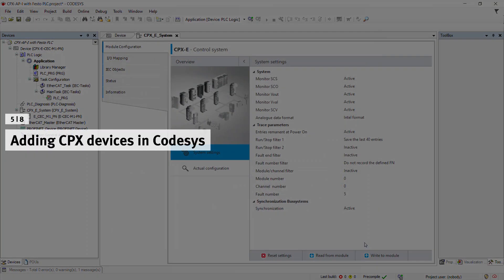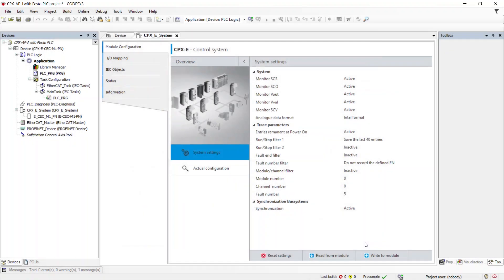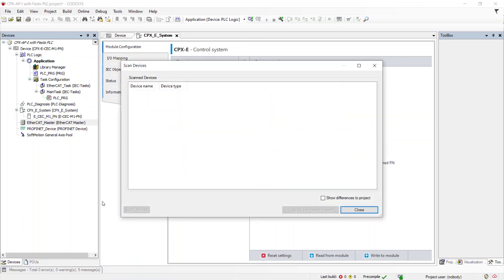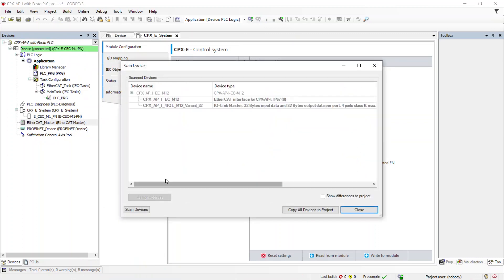Adding CPX devices in Codesys. Right-click on EtherCAT Master and click Scan for Devices. The devices connected to EtherCAT Master will be displayed. If they are not displayed, compile and download the project to the controller and scan again. To add the scanned devices, click on Copy All Devices to Project.